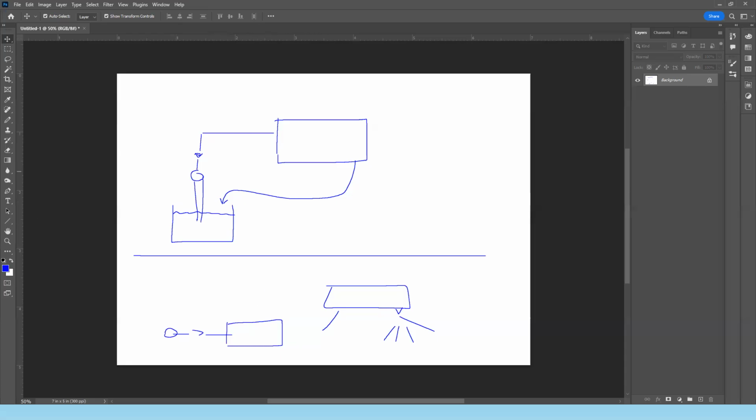When it comes to the air, we do have a pump here. We might have some check valve going on. And yes, we will have some reservoir tank, but the purpose of the reservoir tank in the pneumatic system is not the same as the purpose of the reservoir in hydraulics. The purpose of the tank is just to keep enough pressurized air so you have the reserve.